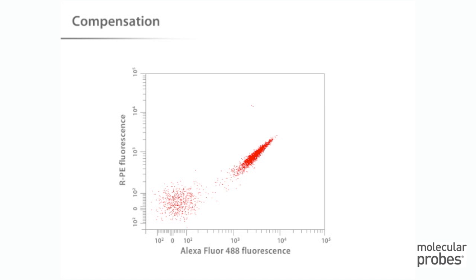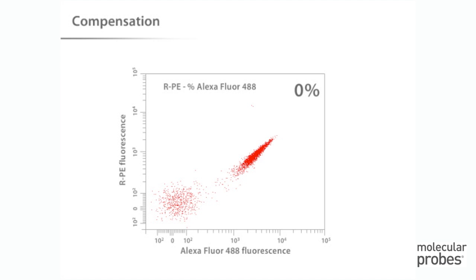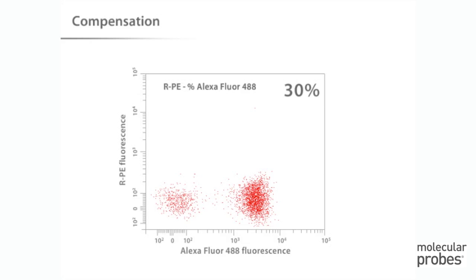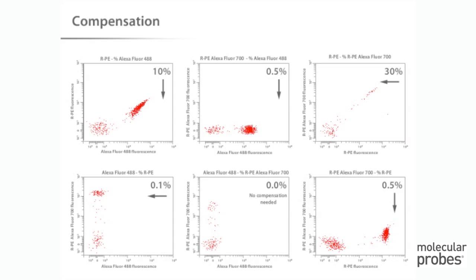The Alexa Fluor 488 labeled population is compensated so that the mean fluorescence values in both the positive and negative populations are equal in the RPE channel. Practically, this is performed for each event by subtracting a percentage of the fluorescence in the Alexa Fluor 488 channel from the fluorescence in the RPE channel. Depending on the instrument and software used, compensation could be set either in the instrument hardware before the sample is run or within the software after data collection. Every fluorophore combination that shows spectral overlap must be compensated.